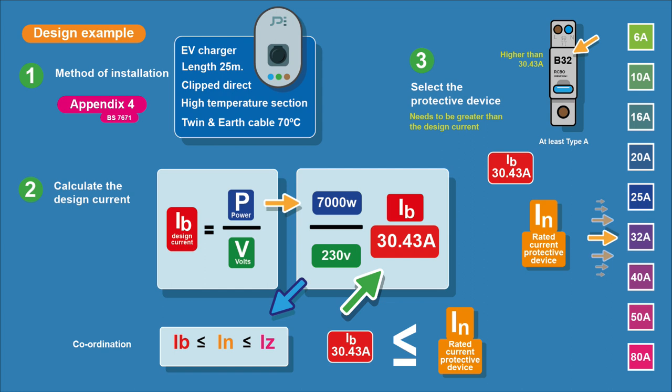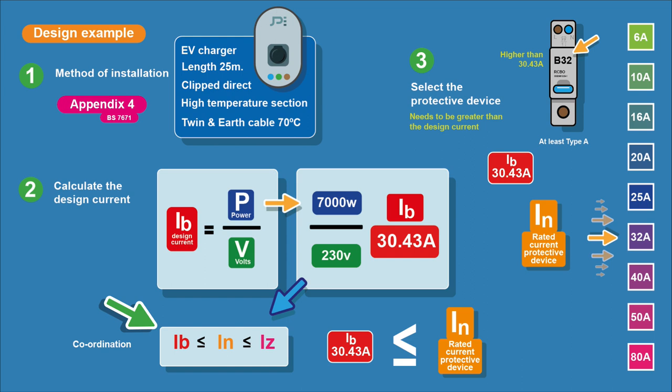Next we select the protective device. This is the IN, the rated current of the protective device — the rating printed on the device itself. Following our coordination, IB must be less than or equal to IN. The next size up from 30.43 amps is a 32 amp protective device. There are other things to consider for an EV charge point: we're using an RCBO, it has to be double pole with switched neutral. Because the EV charger can produce DC current, we need a protective device that can handle that — so it needs to be at least Type A. So our IN is 32 amps and coordination is achieved.